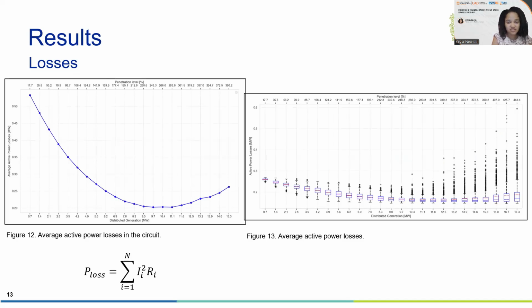After that, we evaluated losses. In the image on the left, we have average losses registered in each penetration level for the whole circuit. Here we can see there is a minimum that is found when generation meets demand. But this is true, in this case, for all the load connected to the substation, as the Almendro circuit is not isolated from the other loads in the substation. On the other hand, we can find a function that relates renewable energy integration with power losses, finding that there is a reduction of 3.33% per megawatt of installed capacity.